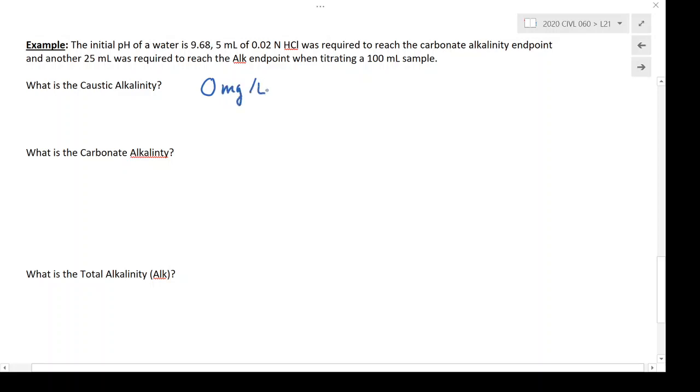because our pH is less than the caustic alkalinity endpoint, which is typically about 10.8, somewhere around there. And so it's going to be 0, so we'll have no caustic alkalinity because we're starting out below that endpoint.